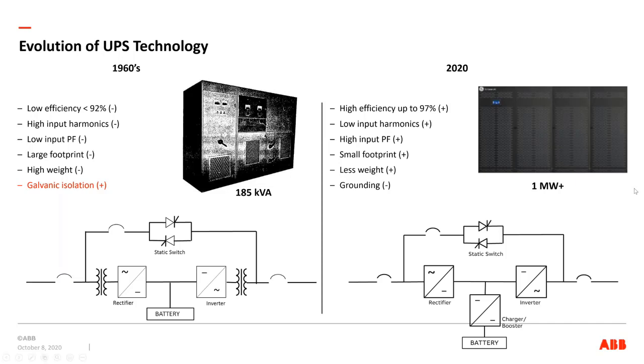UPSs used to be what we would refer to as transformer-based UPSs, with a lot of magnetics and a lot of filters, which were badly needed to filter out harmonics and to protect the fairly fragile semiconductors that were used in the early years. Today we need very little filtering. We do not need the transformers anymore because we have rugged semiconductors and fast switching devices. The benefit is that footprint, weight and losses have gone down dramatically because we've gotten rid of a lot of that heavy magnetics, transformers and filters in the UPS. We don't need them anymore.